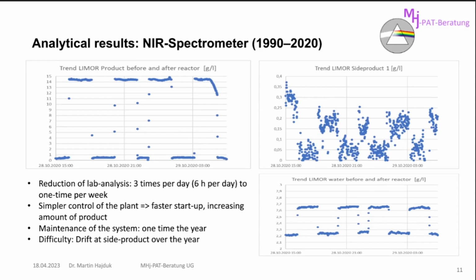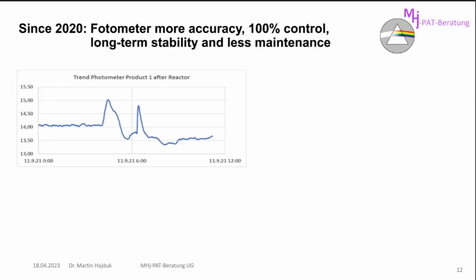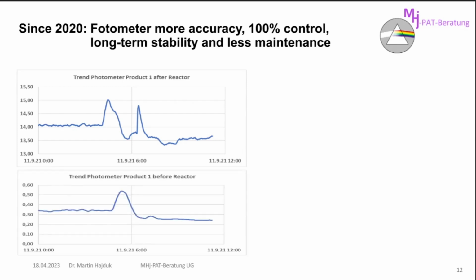What can we say about this analytics? We can reduce the lab analysis. Normally we have 3 times per day, which is normally more than 6 hours per day. And later on, we only make the analysis 1 time a week. We have a simpler control of the plant, faster startup, and an increasing amount of product. For the maintenance of the system, we need 2 days, 1 time a year, for a good maintenance. The difficulty was the drift of the side product over 1 year. We went to a photometer. It's a KISS analyzer. It's not as complicated as a spectrometer.